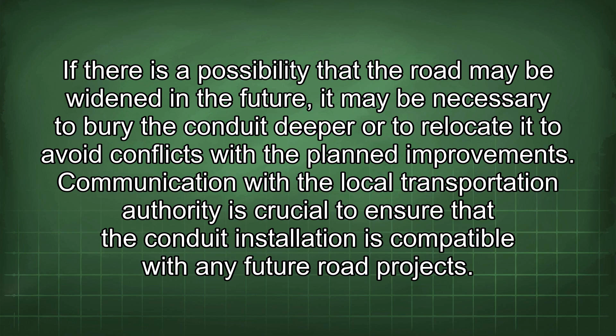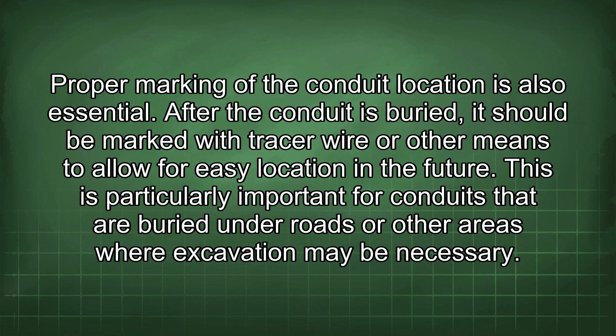After the conduit is buried, it should be marked with tracer wire or other means to allow for easy location in the future. This is particularly important for conduits that are buried under roads or other areas where excavation may be necessary. The tracer wire should be connected to a readily accessible above-ground marker such as a utility pole or a handhole. The marker should be clearly labeled to indicate the presence of the underground conduit.